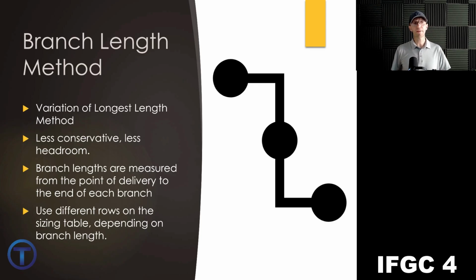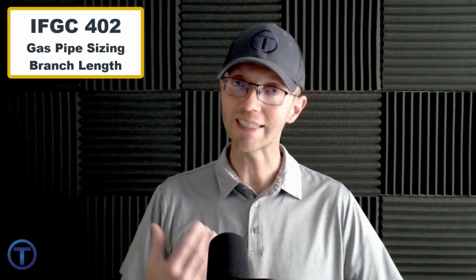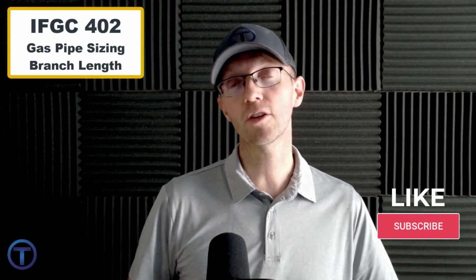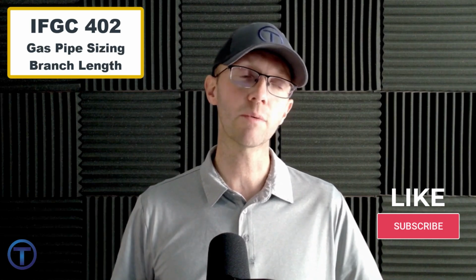One thing you also need to understand about the branch length method is that it is less conservative. There's less headroom. What that means is as you're sizing, you're more likely to undersize if you're using the branch length method. If you want to stay far away from undersizing, then stick with the longest length method. But why would it be important to use the branch length method? If you're trying to save on material costs, this might help because you can dial it in a little closer on the branches and perhaps save some material by not oversizing. So there's kind of a balance there, and you have to decide which one to use.